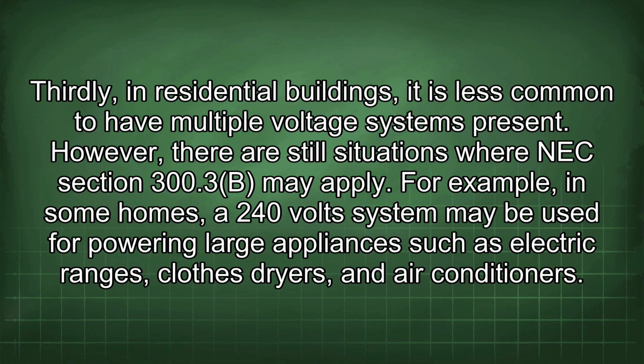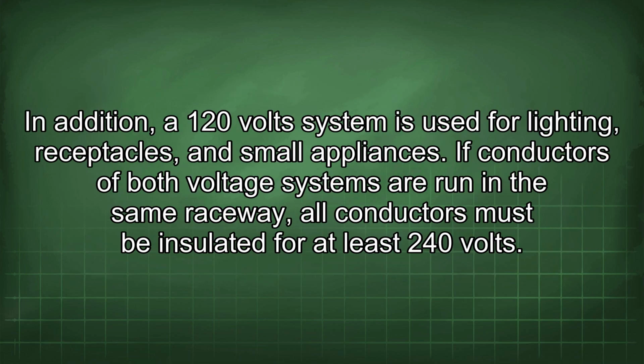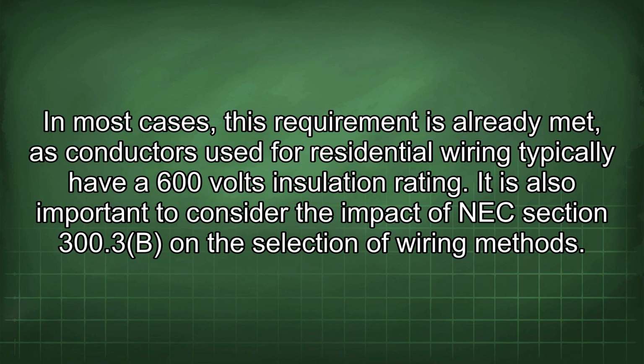Thirdly, in residential buildings, it is less common to have multiple voltage systems present. However, there are still situations where NEC Section 300.3b may apply. For example, in some homes, a 240-volt system may be used for powering large appliances such as electric ranges, clothes dryers, and air conditioners. In addition, a 120-volt system is used for lighting, receptacles, and small appliances. If conductors of both voltage systems are run in the same raceway, all conductors must be insulated for at least 240 volts. In most cases, this requirement is already met, as conductors used for residential wiring typically have a 600 volt insulation rating.